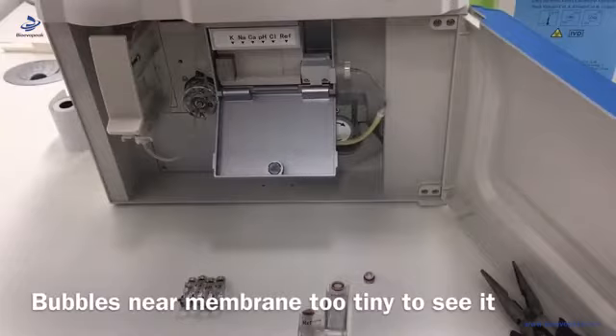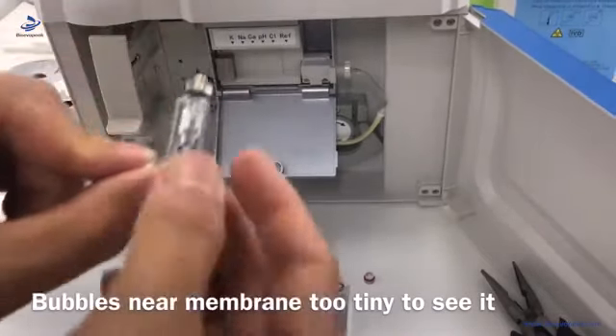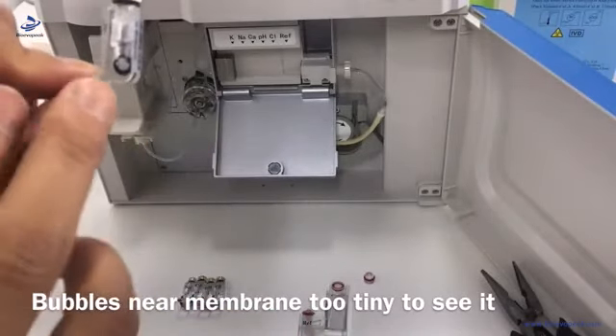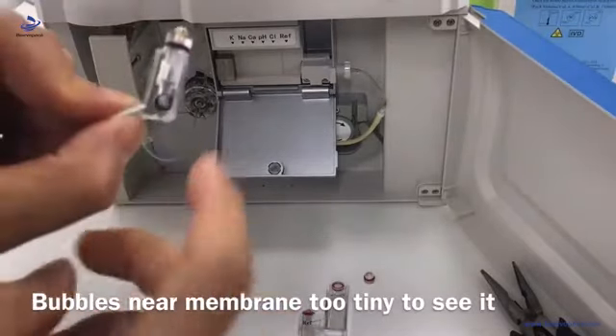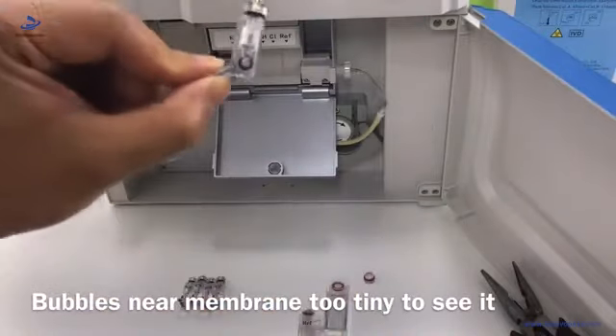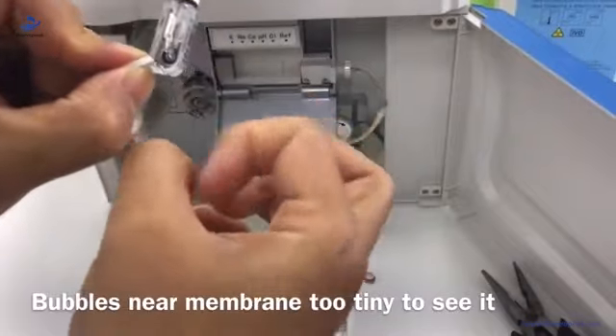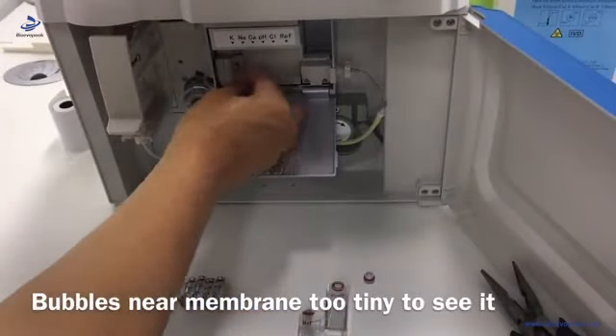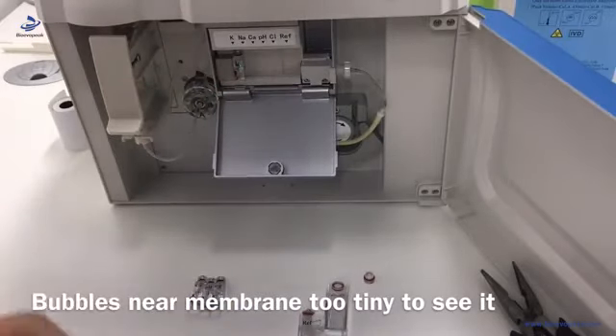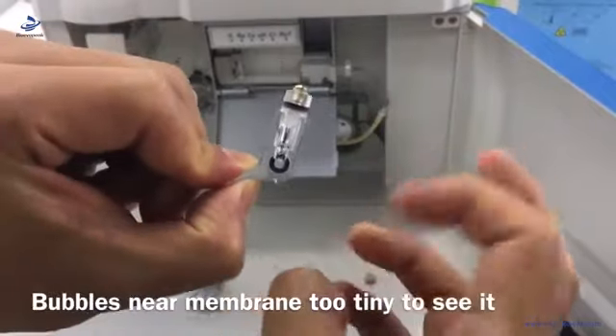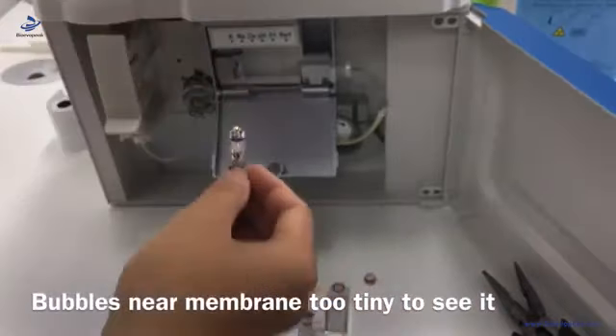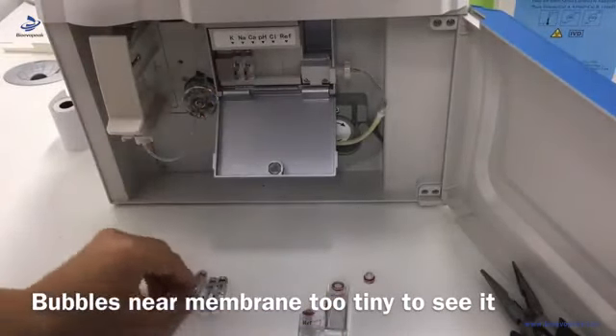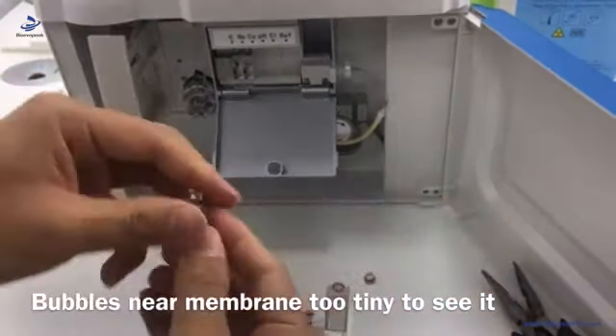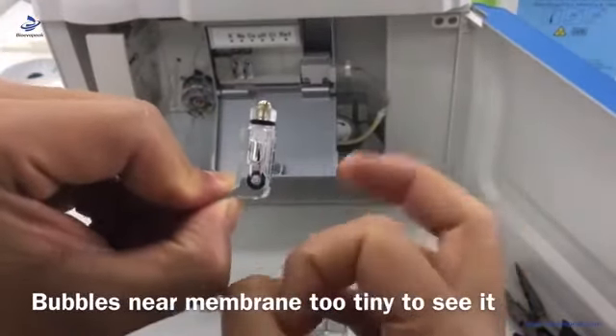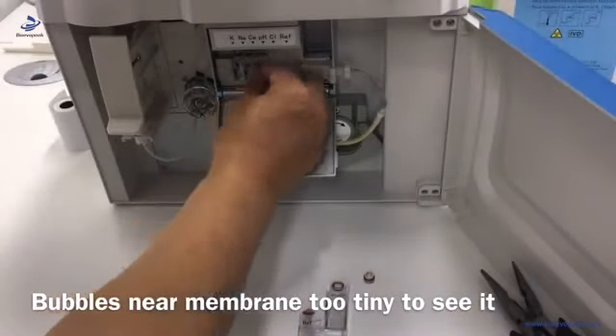Now let's do the installation for the electrodes. This is a normal electrode. We hold it in this position, and there are tiny bubbles inside that we can't see. We hold it like this and use our finger to flip the bottom of the electrode. We need to do it hard, and then we can remove the tiny bubbles. You have to do it before installation for each electrode. Now here is just the demo. I already did it for each one of them, so we can install them quickly.